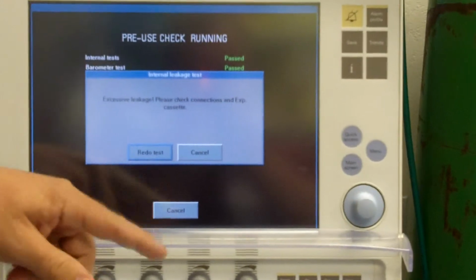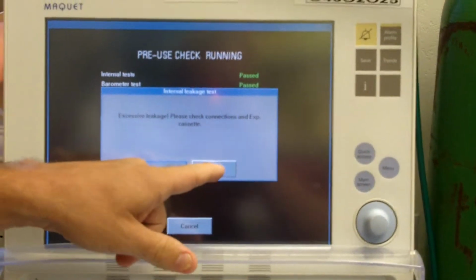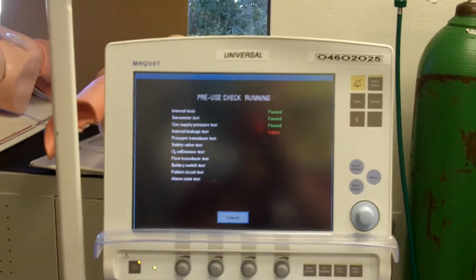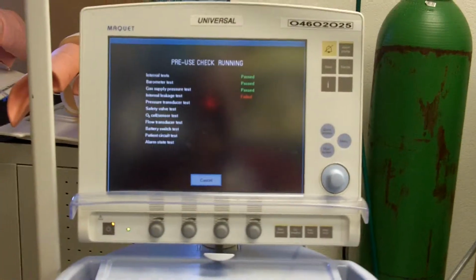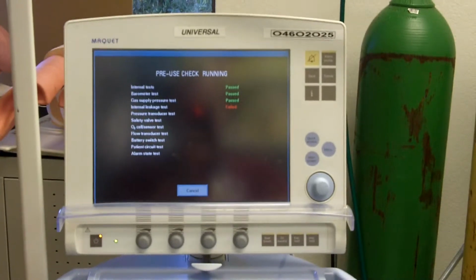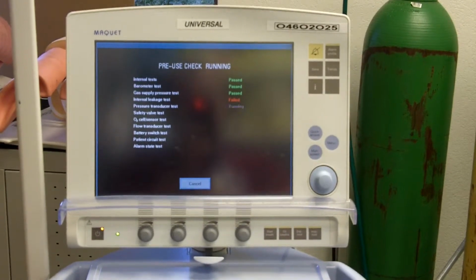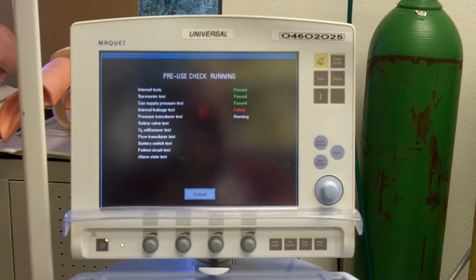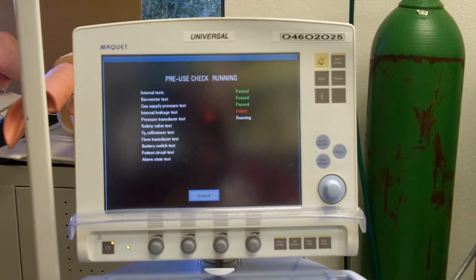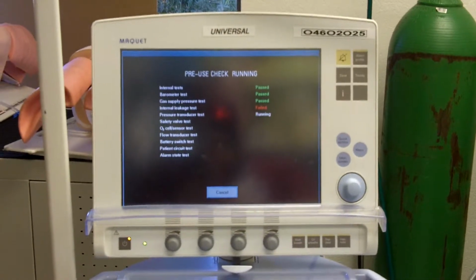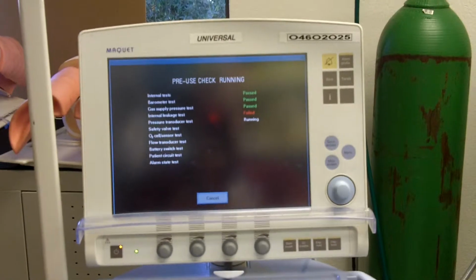Of course, it's not going to work. Excessive leakage because we don't have the Ballard on and we don't have it capped off, but that's all right. We'll go ahead and cancel. Keep going with it. Of course, it'll show you if it failed or anything. And this basically is your initial startup check, your pre-use checks, to make sure that there's nothing wrong with the equipment, prevents lawsuits, make sure that the patient has proper care, best care we can provide.